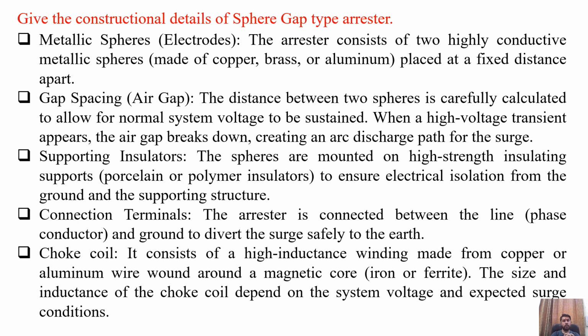The constructional details of sphere gap type arrester. So the sphere gap type arrester consists of metallic spheres that are treated as electrodes. The arrester consists of two highly conductive metallic spheres made of copper, brass or aluminum placed at a fixed distance apart, which creates an air gap. So the second component is the gap spacing or air gap. The distance between the two spheres is carefully calculated to allow the normal system voltage to be sustained.